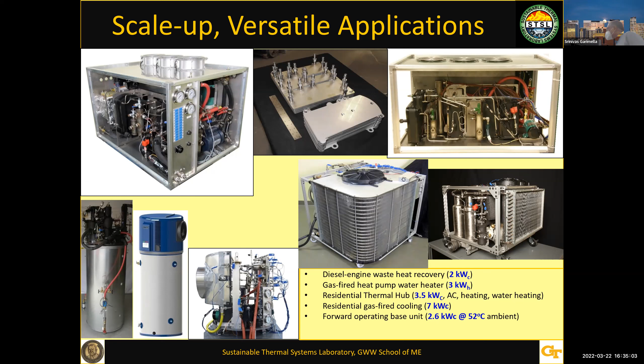With this, we were able to reduce the energy consumption. For every BTU of heat that goes into the system, due to the heat pumping, the person taking the shower gets 1.7 BTU. So we're reducing the gas consumption, the fuel consumption to provide the heating by almost 40 to 50%. So these are some of the innovations we have done.